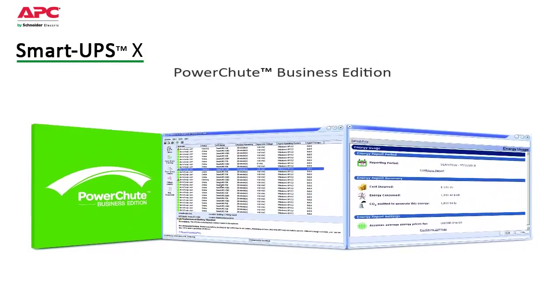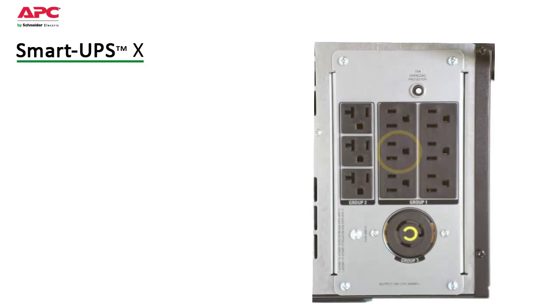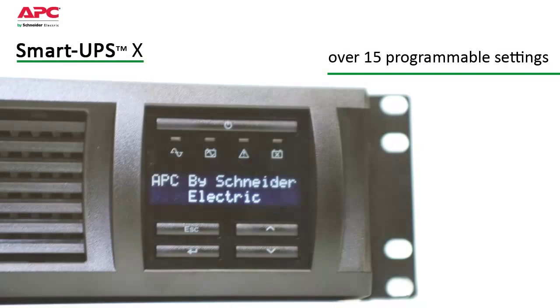Included is APC's PowerChute Business Edition software. Compatible with most server operating systems, it provides innovative monitoring and control and graceful unattended shutdown in extended outage situations. A switched outlet group can be controlled like a UPS within a UPS to further customize settings and provide discrete reboot of hung devices, sequenced on-off, and non-critical load shedding to preserve on-battery run time.